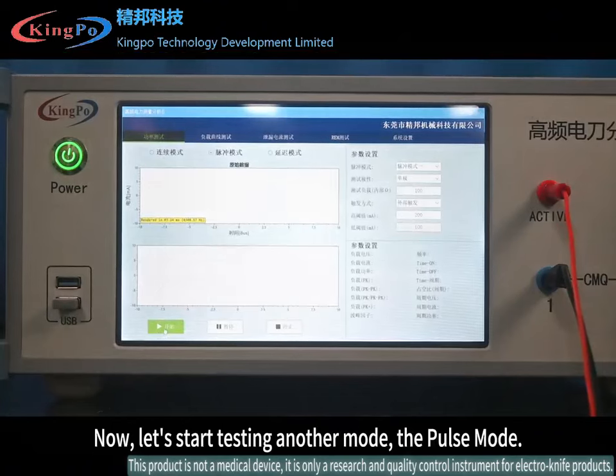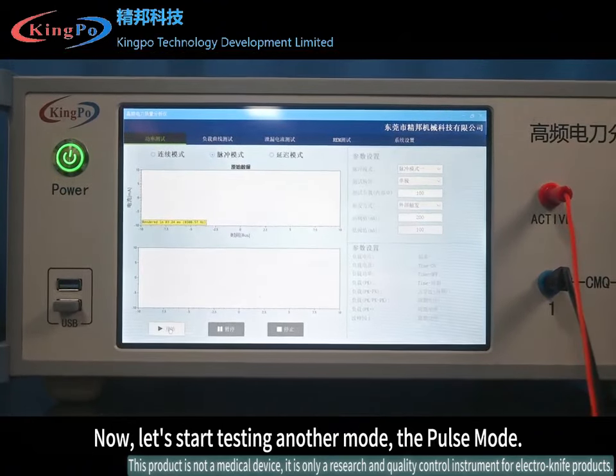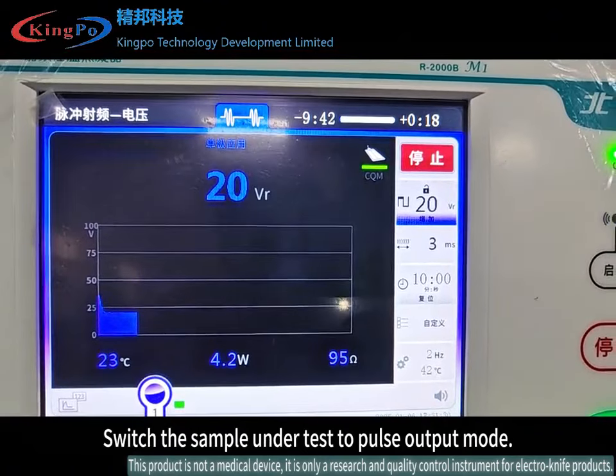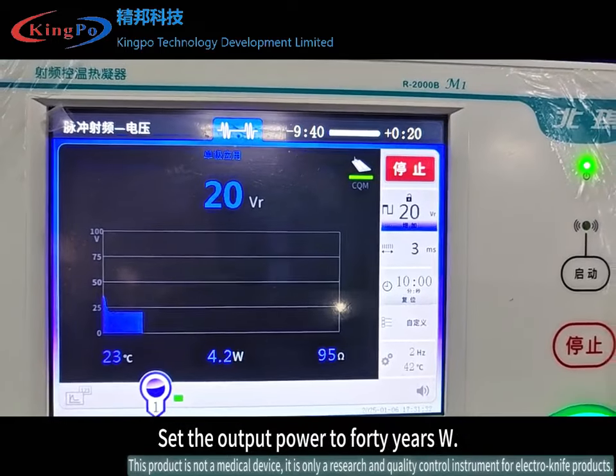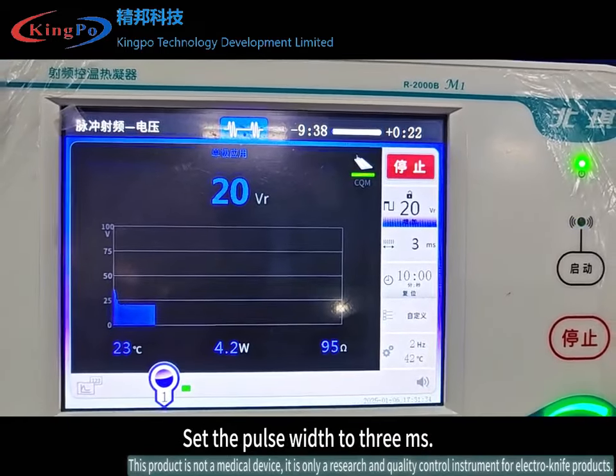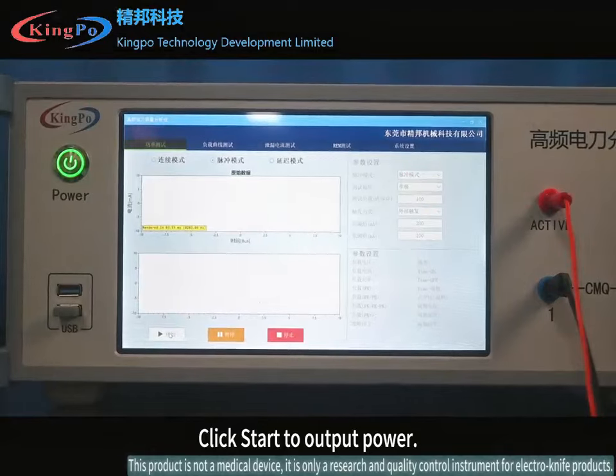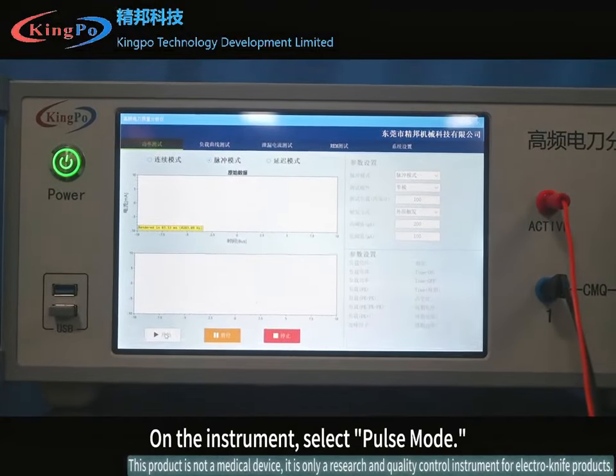Now, let's start testing another mode, the pulse mode. Switch the sample under test to pulse output mode. Set the output power to 40 W. Set the pulse width to 3 ms. Click Start to output power. On the instrument, select Pulse mode.